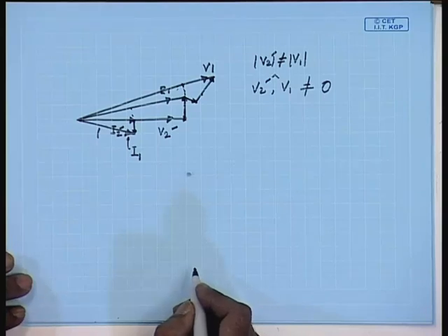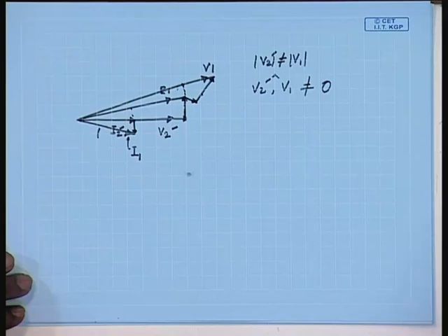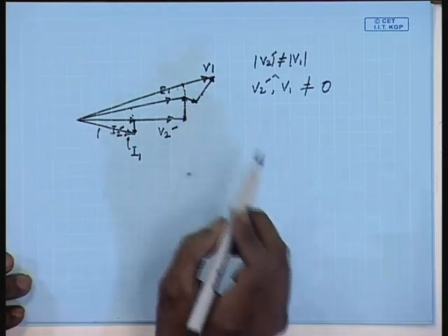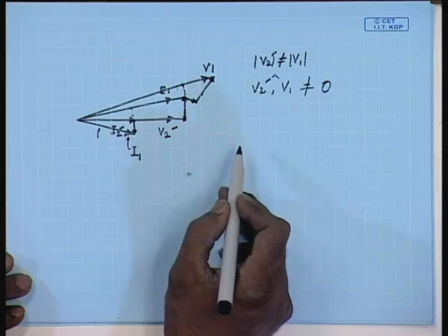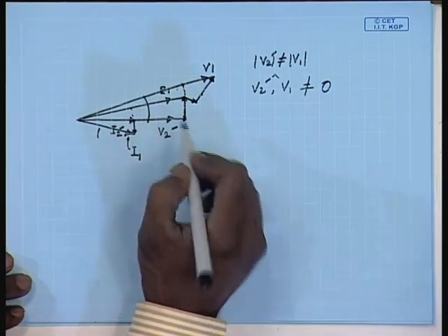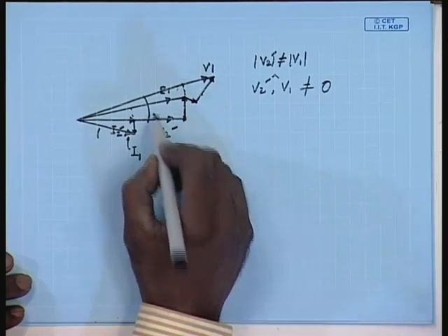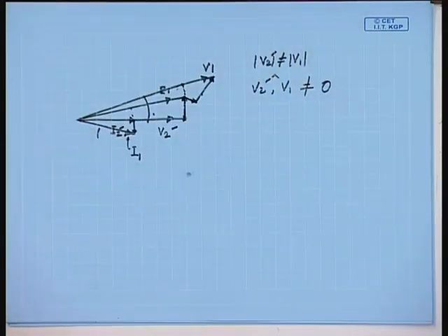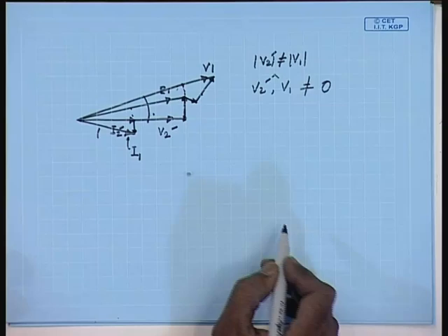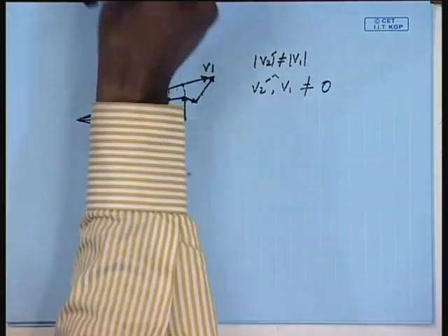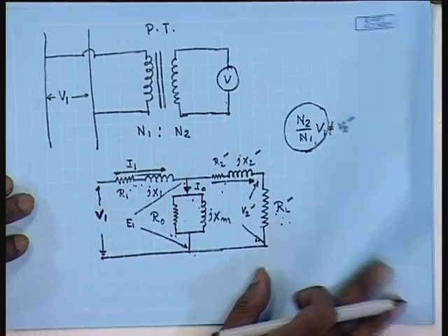Hence, in voltage measurement there will be an error introduced due to the series impedance, and while in power measurement not only the magnitude, but the phase angle error between V1 and V2 dash will become important. So, constructional features should address these problems. One should make sure that the no load current is very small, as well as the series impedances of the potential transformer are very small.